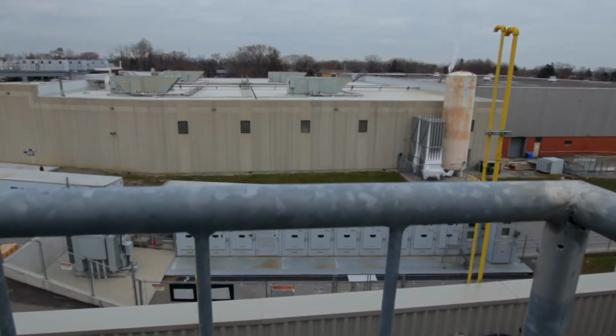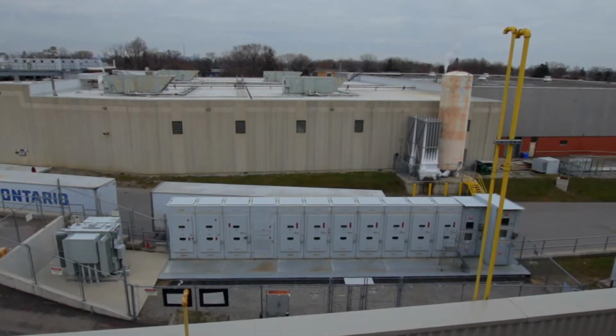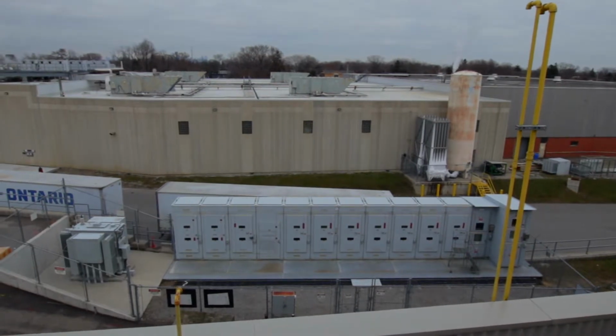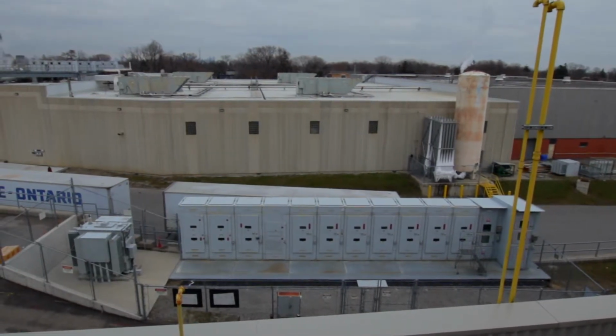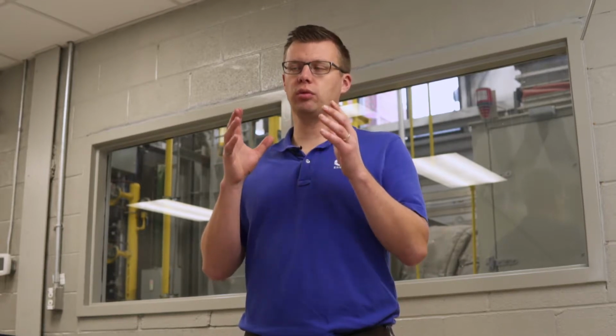So here we have the generator making power at 13.8 kilovolts, 13,800 volts. After the power leaves the generator, it goes into what we call the 15 kV class of switchgear. There's a metering cell in there, and then there's a generator breaker. That generator breaker provides protection for the generator. If something were to happen out on the grid, that breaker would protect the generator from anything untoward happening to it.